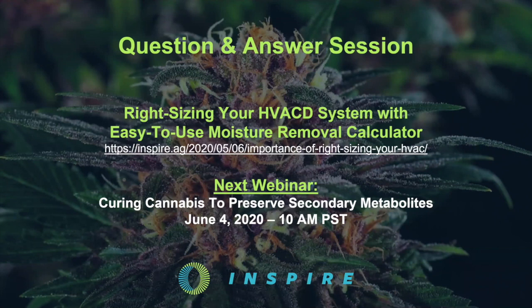But beyond all that, making smart light choices will probably help drive the efficiency of the facility. And also, we know that LED rooms, which are much warmer, have a much easier ability to dehumidify that air using less compressor tonnage. So those factors all combine, and we could see energy use 50% lower in an efficient building compared to a standard building, a legacy system that was being built and designed, I guess even today, but usually we saw them mostly 5 years ago or so.